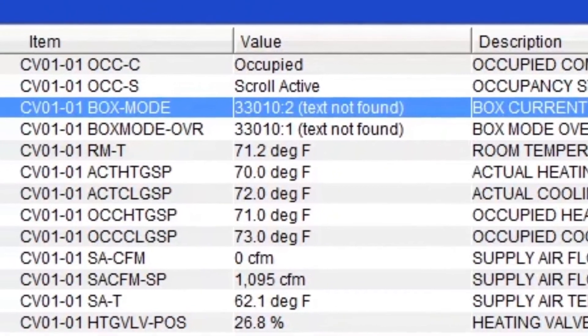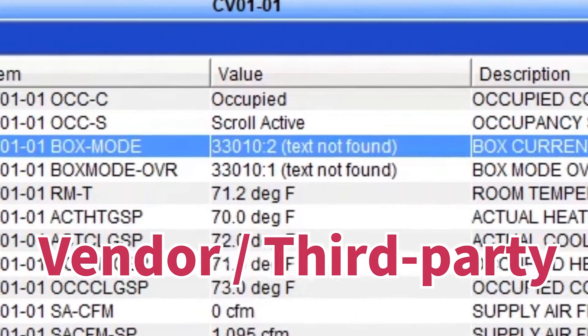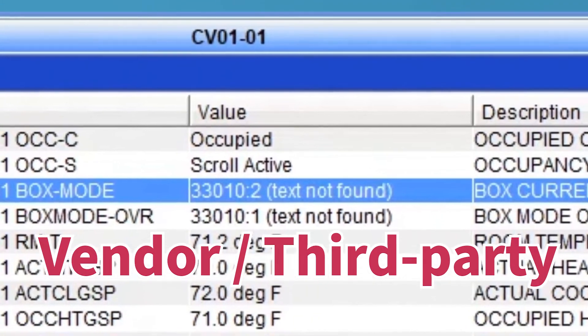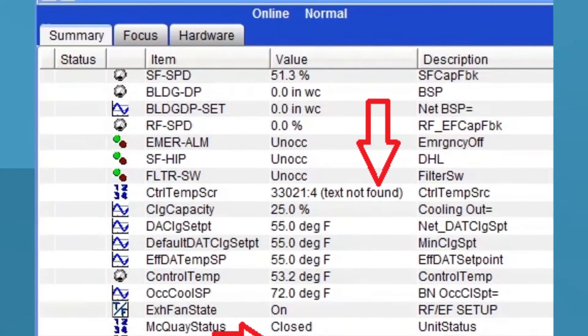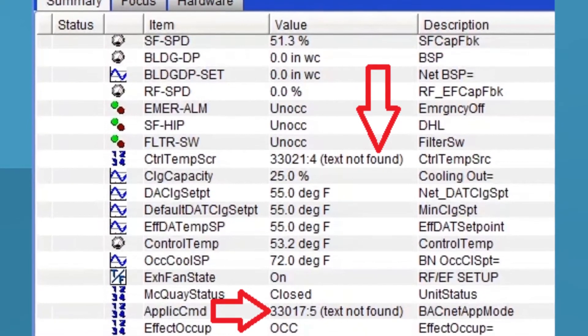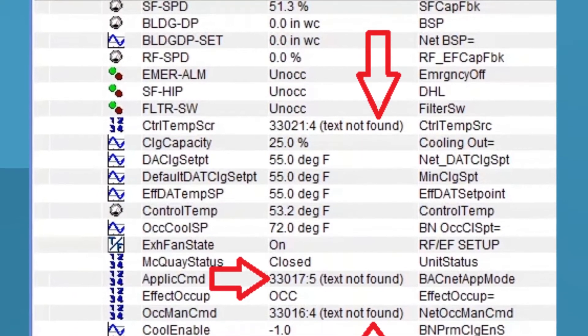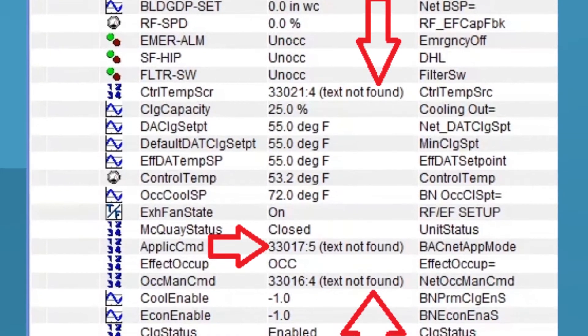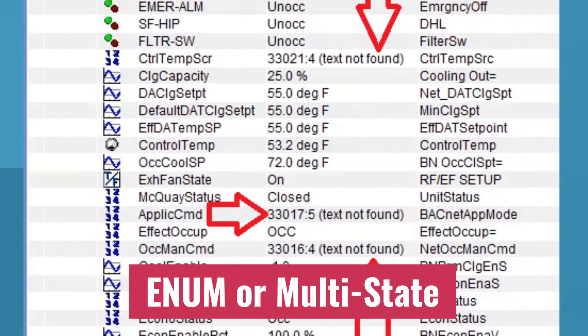And why is that? Well, this has to do with vendor or third-party BACnet devices that you map in Metasys, meaning non-Johnson control devices. And this happens to your enum points or enumerators. These are the points that have multiple states.